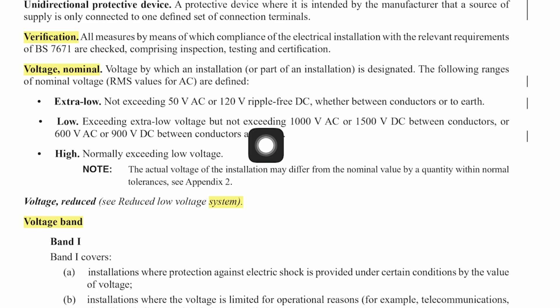And then can you see this? It's 600 volts AC or 900 volts DC between conductors and earth. So can you see that if you've got two conductors, you've got two layers of insulation to protect you from shorting out, but when you've got one layer of insulation to earth, the voltage is going to be a little bit less, and that's the reason why it comes in there. So if you understand that, you'd have gained a mark. If you didn't appreciate that, you just threw an easy mark away. Anyway, not to beat you up on that one.